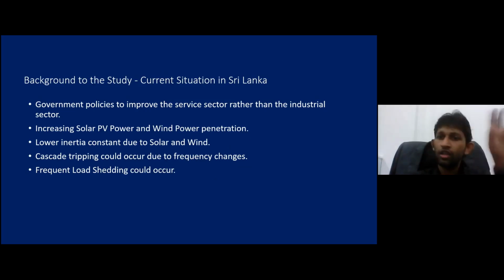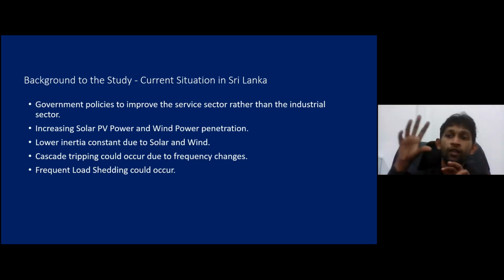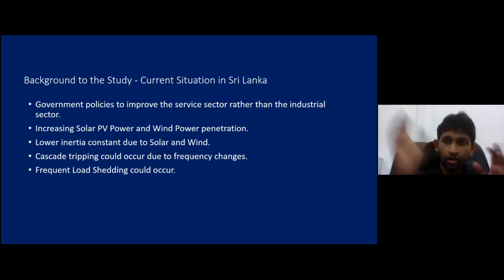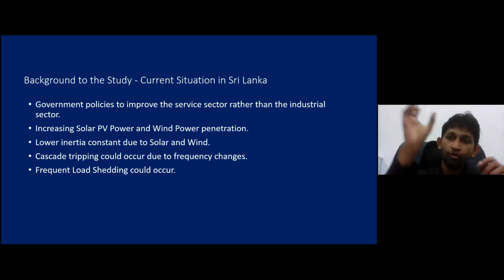Now in Sri Lanka, the problem is this inertia constant, in seconds. Currently, the inertia constant of the system is 3.9 seconds. If we replace all the installed solar embedded generation with synchronous generators, we can improve this to 4.2 seconds. So there is a significant drop from 4.2 to 3.9 seconds.